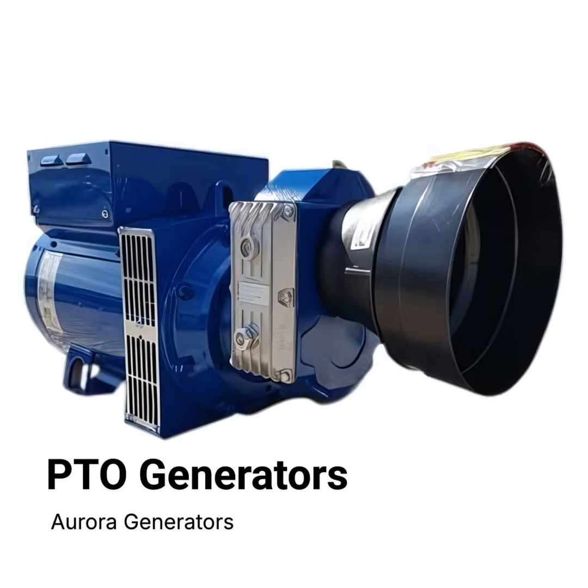The kVA rating is fundamentally about the alternator's power handling capability, as we said, but what limits that capability is mainly heat. Heat inside the windings. Yes. The insulation materials used around the copper wires in the stator windings have temperature limits. The kVA rating is largely determined by how much heat those insulation systems can withstand over the long term, linked to the expected operational life. So better insulation means a potentially higher kVA rating or longer life. Or both. It's about managing the heat generated by the electrical current.